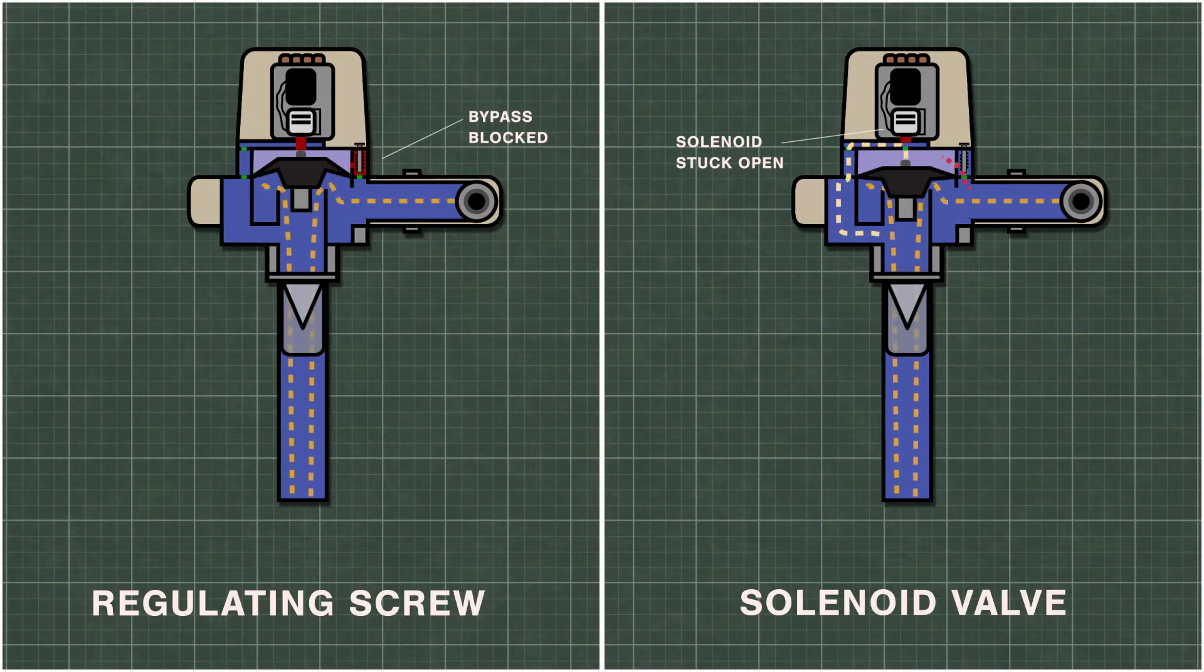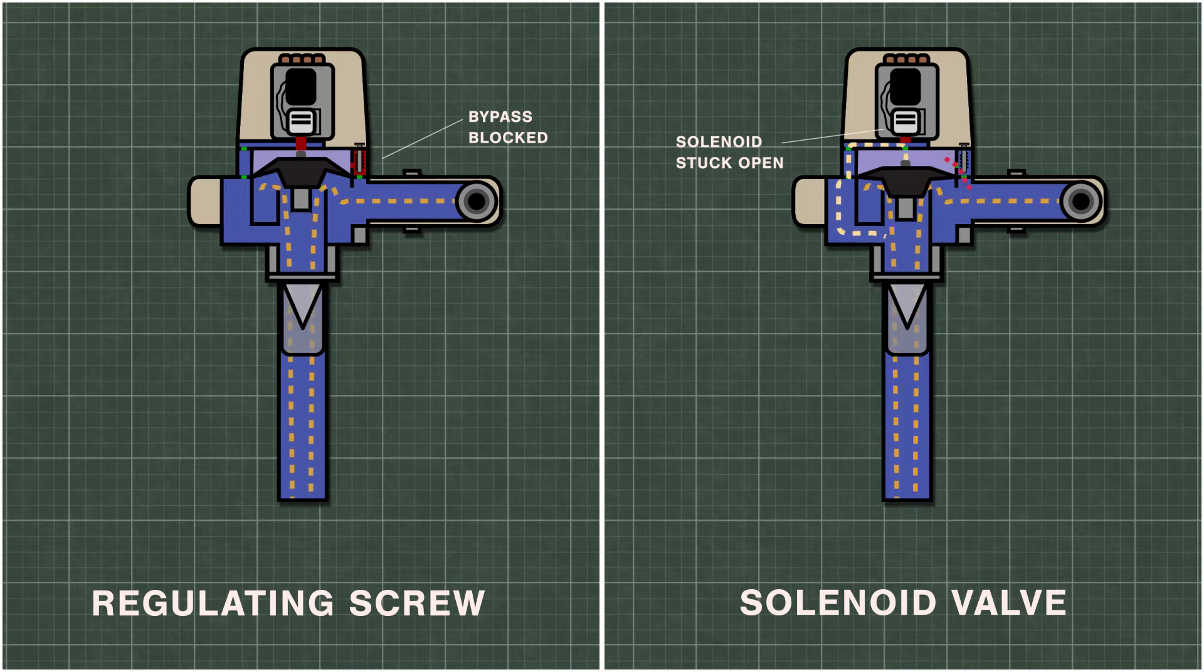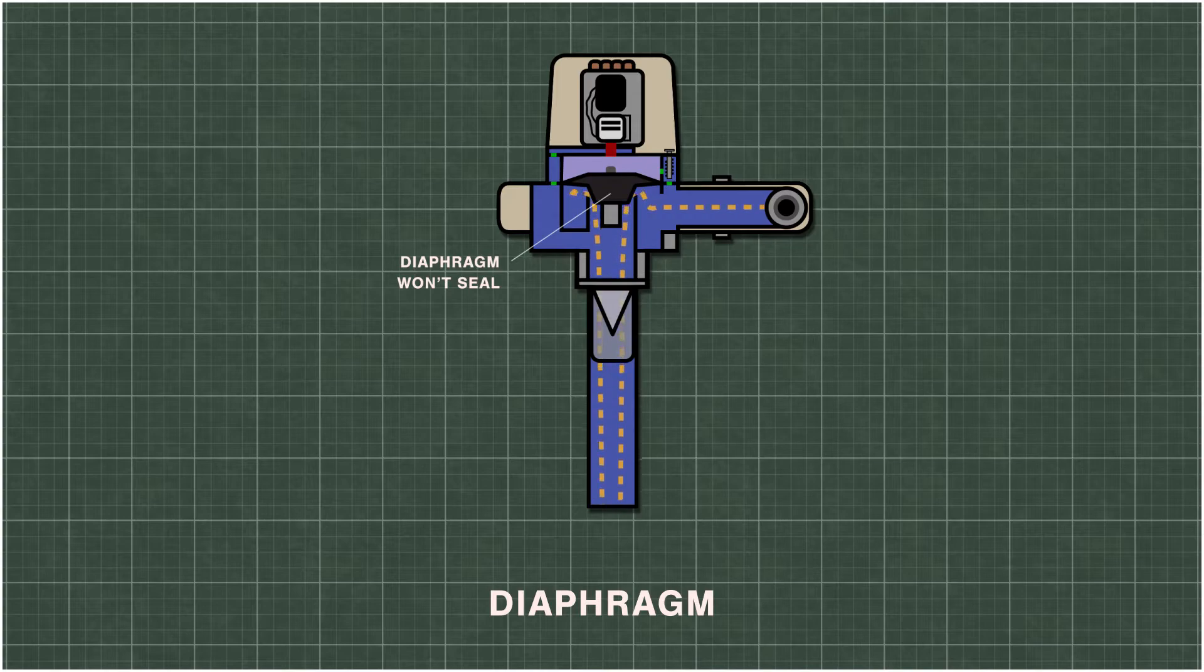Continuous flushing can happen when the upper chamber does not fill with water. Either the bypass isn't letting in enough water or the solenoid isn't closing. Another cause can be the diaphragm. If it's stuck open, then the water will continue to flow during a flush.